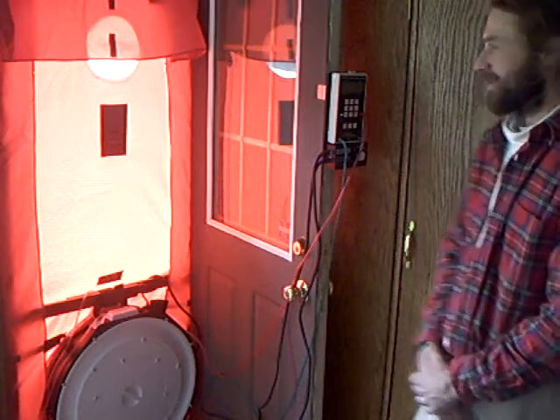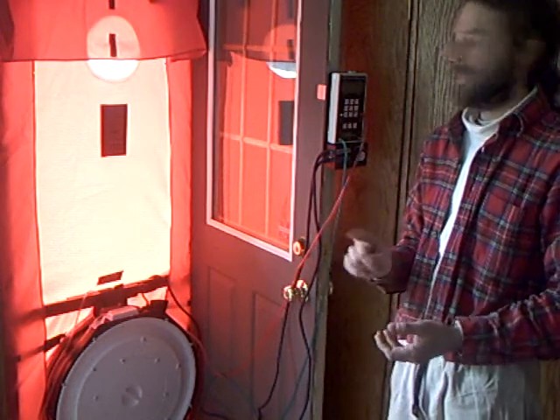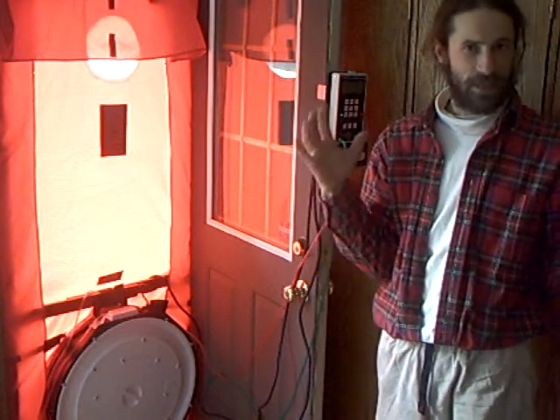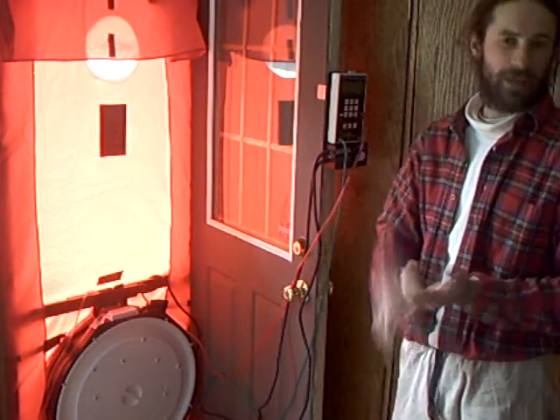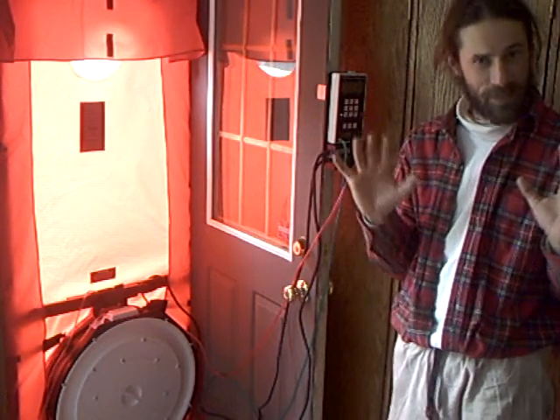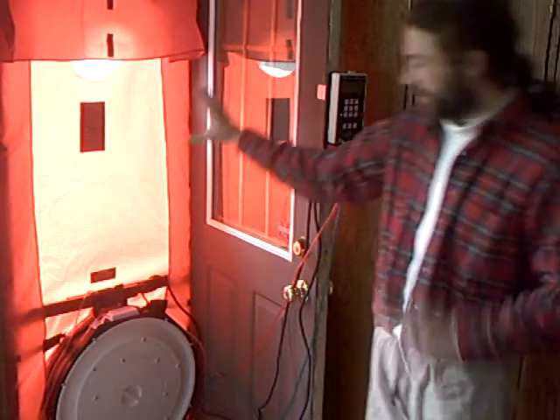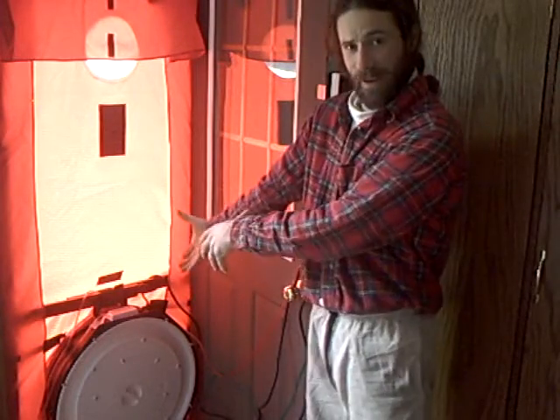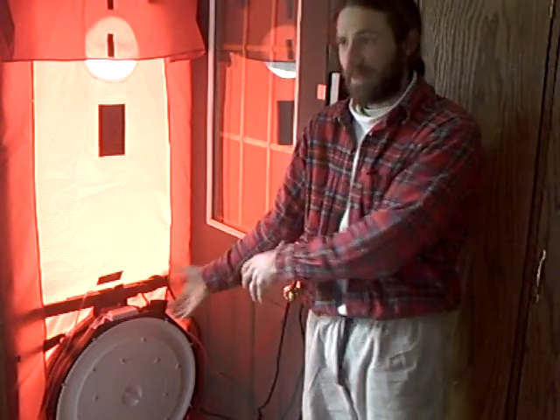Yeah, definitely. The blower door is used for a couple of things primarily. One is to depressurize the house. What we do is we create wintertime conditions in your house by closing all the exterior doors, locking all the exterior windows, making the house as tight as possible. Then we hook the blower door up in an exterior doorway and we depressurize the house, meaning we blow air out the fan, and as air is being blown out the fan, it is replaced by air through all of the cracks or gaps in the air barrier.